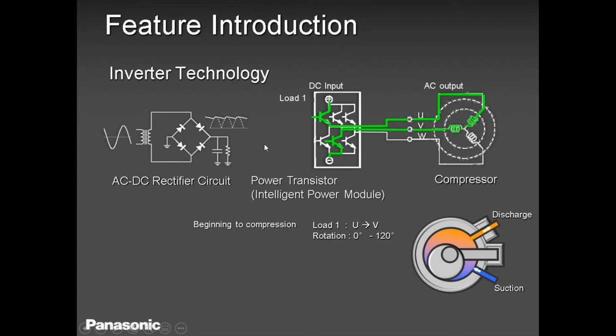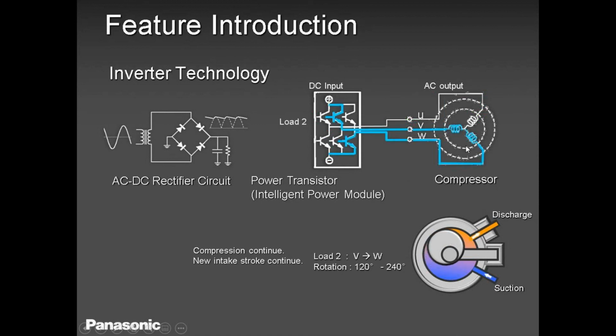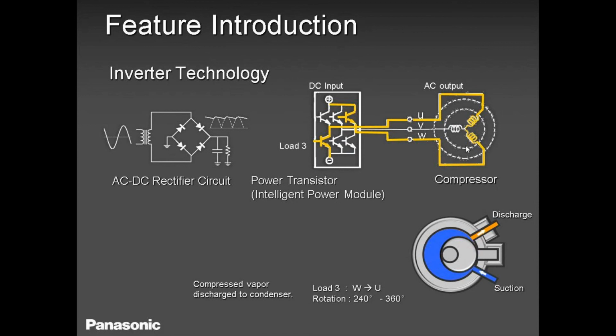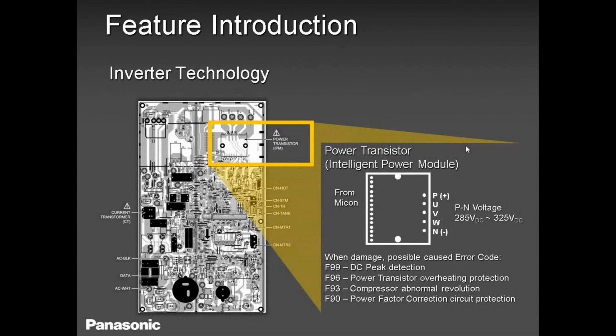Basically, this is how our unit looks like outside. That's the inverter rectifier circuit board, the power transistor, which is the IPM, intelligent power module, and that's our compressor. All these two items along with the control board come in one piece to drive the compressor as well as the fan. AC voltage comes in, it's converted into DC. DC goes through the IPM module PCB. It converts from single phase to three phase, and that's how you run your compressor.